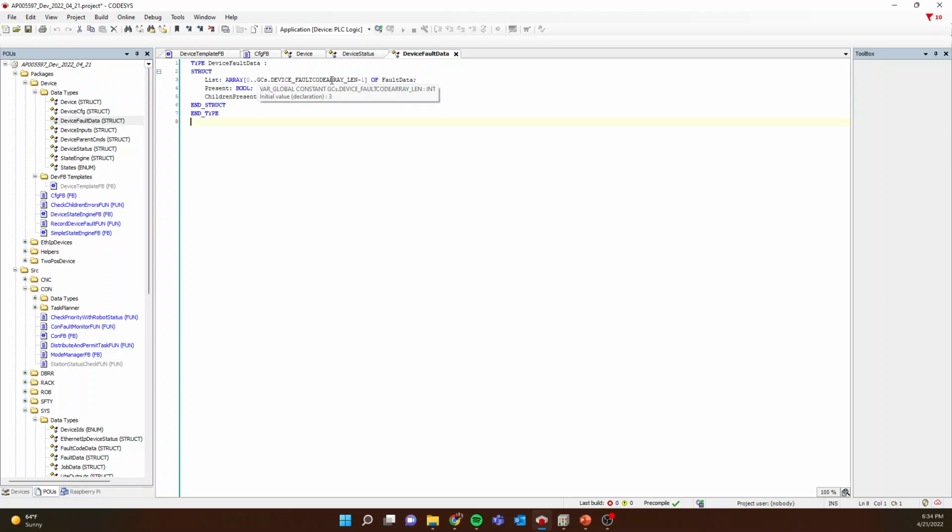I'm not recording more than 3 active errors at once. If you're triggering a ton of errors in your logic, then you may be confusing the operator. So you might want to rethink how many errors you allow yourself to trigger at once. That's why it's limited to 3, just to reinforce that mentality.